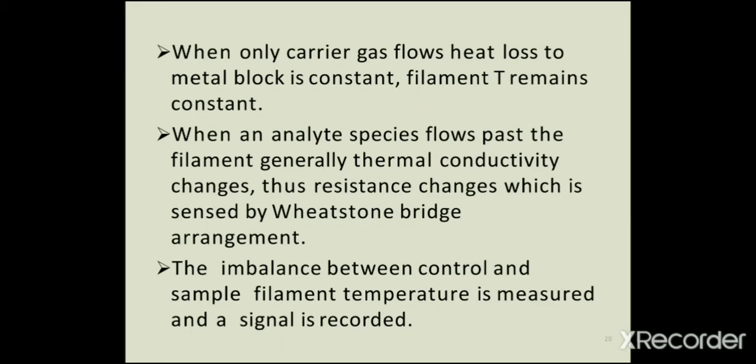So when there is a flow of only carrier gas, the heat loss will be constant and there will not be a change in the temperature of the filament. When the same carrier gas passes along with the analyte, the heat lost will change. So the temperature of the filament will change, and this can be sensed by a Wheatstone bridge arrangement. Then the imbalance between control and sample filament temperature is measured and the signal is recorded.